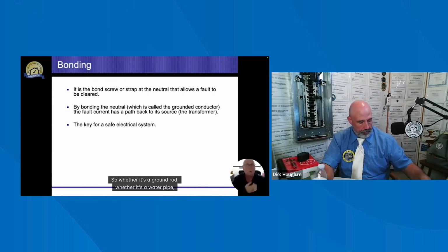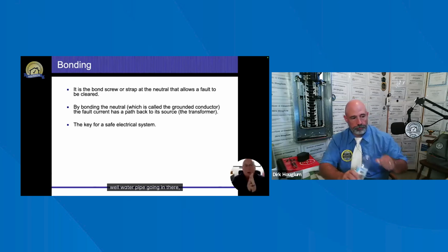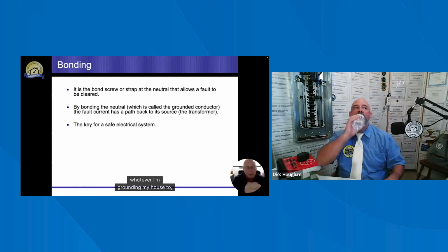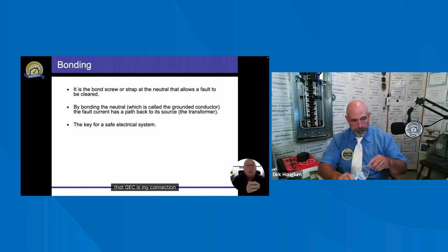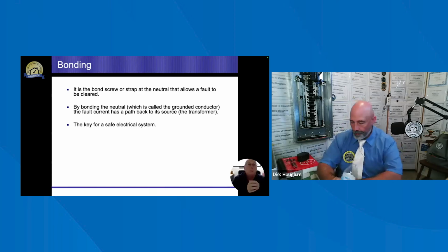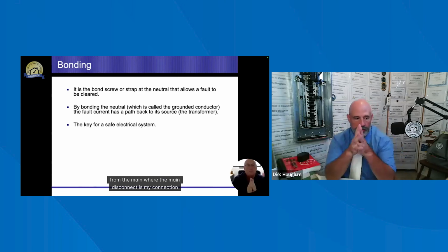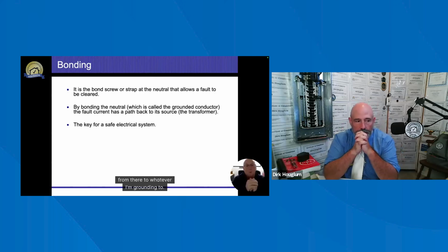So whether it's a ground rod, a water pipe, a ground ring, a Ufer ground, a ground plate, a well water pipe going in there, whatever I'm grounding my house to, that GEC is my connection from the main disconnect to whatever I'm grounding to. That grounding electrode conductor does have some specific rules to it, all right? And I don't have them written down. So if you have a pen and paper, I would suggest that you write the following down. I'll try and go a little bit slow.